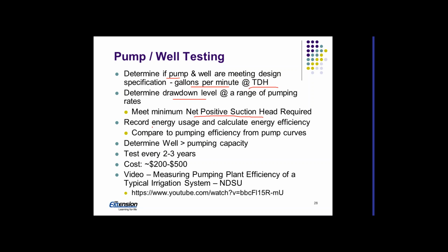So what we're going to do is we're going to run this test. We're going to record the energy usage, and then we can calculate the energy efficiency and compare it to the pump curves and figure out the efficiency. So this is recommended every 2 to 3 years. Typical cost is $200 to $500. And there's a very nice video that Tom Shearer did from North Dakota State. It's about a 15-minute video if you want to review that on how to do one of these tests.